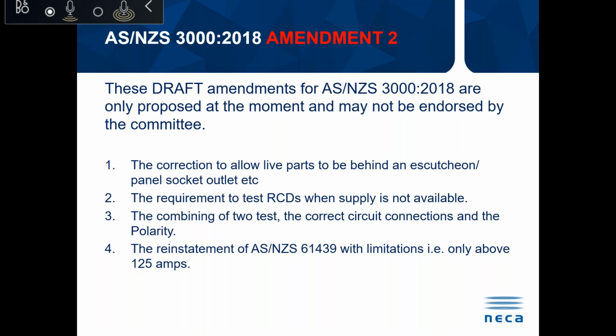There's a planned requirement to test RCDs when supply is not available. This is currently exempt in Australia because you need to have power onto the RCD to use the test function on the RCD.